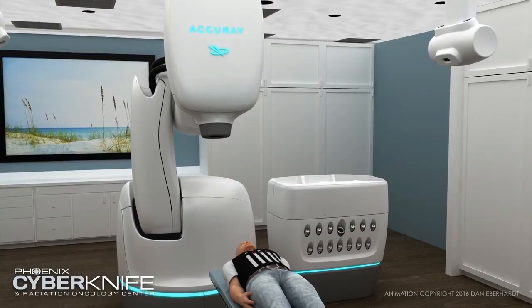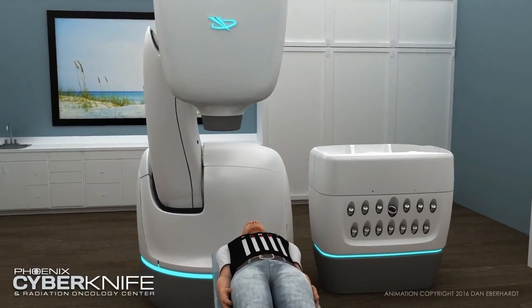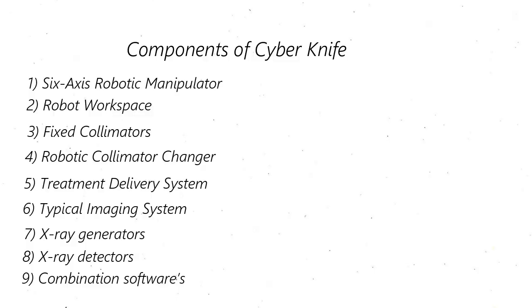Let's look into the components of a CyberKnife. The major components of the CyberKnife are the 6-axis robotic manipulator, the robot workspace, fixed collimators, robotic collimator changer, treatment delivery system control console hardware, typical imaging system, x-ray generators, x-ray detectors, and combination software.